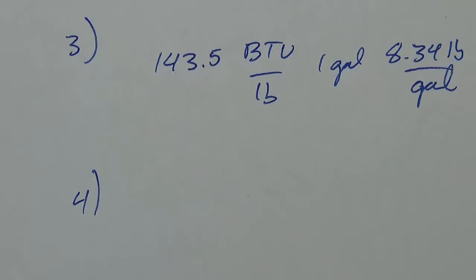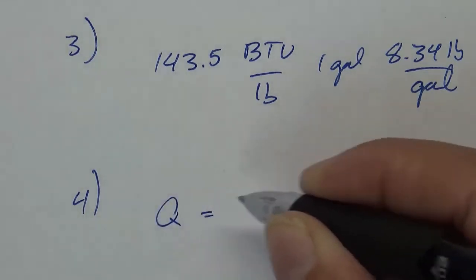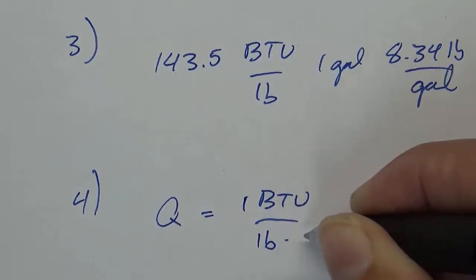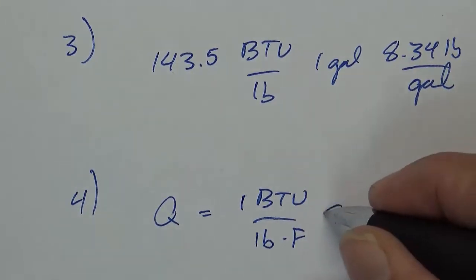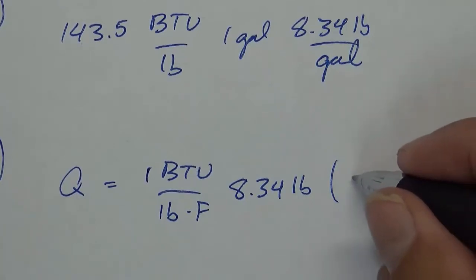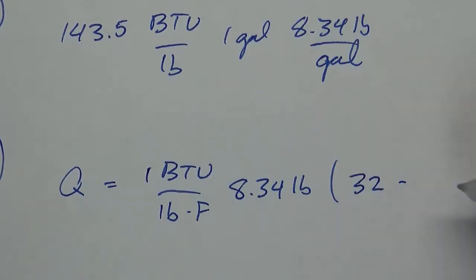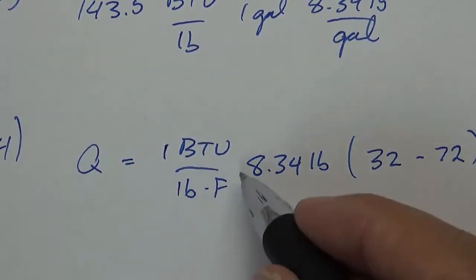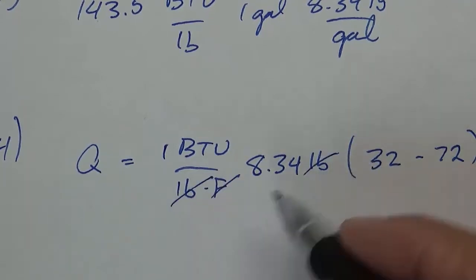Right. Now the last one, number four. What is the amount of heat energy in BTU that must be removed from a gallon of water at 72 degrees to lower the temperature to 32 degrees? So here's my formula: one BTU per pound per degree F. I'm just going to write the 8.34 pounds here because we know that. Now we've got the final temperature, which is 32, minus the initial temperature, which is 72. That's going to be F, so that's going to go away, that's going to go away. I'm going to be left with units of BTU.